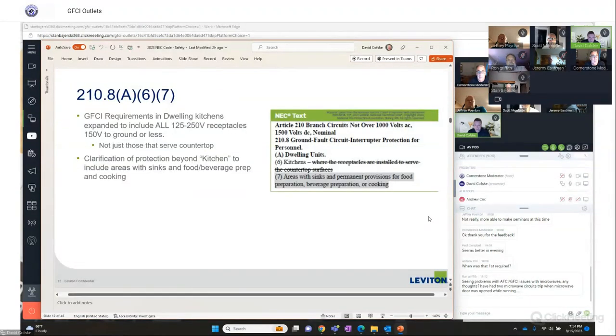Perfect, thank you. Excellent. A couple of code articles that I felt were important to bring up, because I know you guys are inspecting houses. This is new code coming in, but it's things to be aware of, because the requirement for GFCI and AFCI was mostly for 120 volt circuits, like 15 and 20 amp circuits, and they were mostly device and receptacle loads. But under this article, 210.8, it has expanded, and it's basically bringing 240 volt circuits into the mix that need to be protected by GFCI protection.